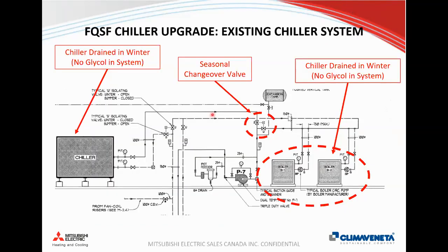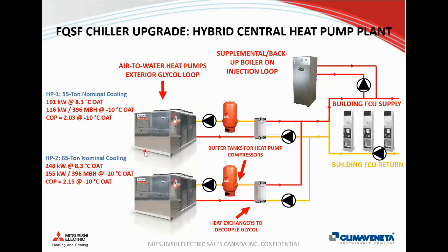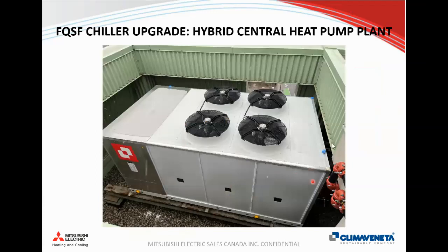So it's typical 2-pipe changeover system for Toronto with just diverting valves for summer and winter mode. So chilled water in the summer, boilers in the winter. Just water throughout this whole system. With the heat pump retrofit, due to the sizes and physical size of their existing chiller, we actually had to split it up into 2 units. So there's a 55-ton nominal heat pump. So essentially half the cooling capacity of the original unit is fitting into the same space.